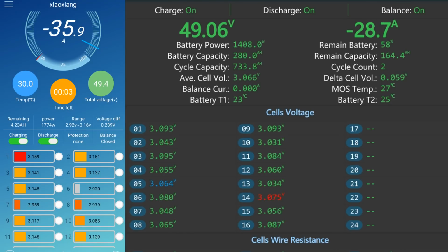But then on the other hand, you know, I said to myself, why should I do this? Because I'm monitoring the system constantly anyway. And if I need to get power out of the battery in such a situation, I don't want the inverter to shut off automatically. I want to control when I take off the load. Maybe I need to drive down the battery to 2.5 volts because it's an emergency or something else, you know.